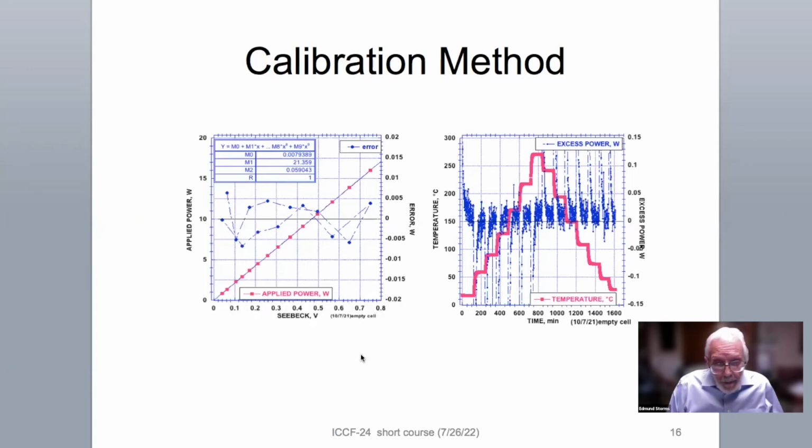This calorimeter needs to be calibrated. And the easiest way to do that is to simply heat the cell using that heating wire that you saw on the outside, but without the sample being present in the cell. So everything's the same. Everything within the calorimeter is unchanged, except it does not have an actual sample present.